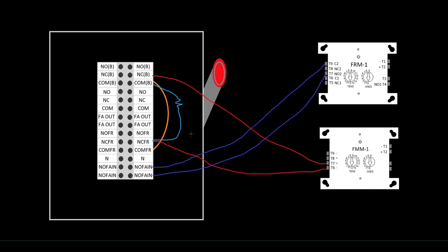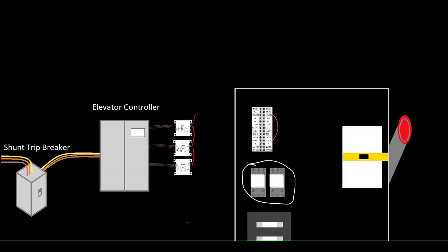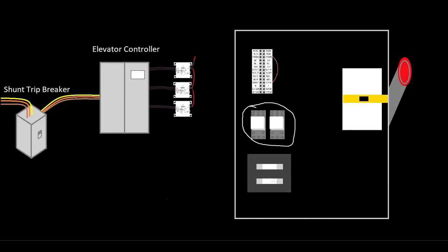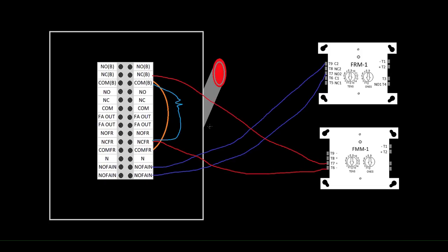Now the downside of this option, because again this is a specific option that you get when you bought the piece of equipment, the downside of it is the only way to test your power supervision is by pulling a fuse out of, you know, one of these. I think there's three fuses on here. I only drew two. You have to pull the right fuse out so you lose the correct phase, and we figured that out the hard way during an elevator final one time. But then after doing it a couple times it wasn't so bad. If you have a fuse puller, you know you're doing it live, but it was a kind of a cool way to test it.